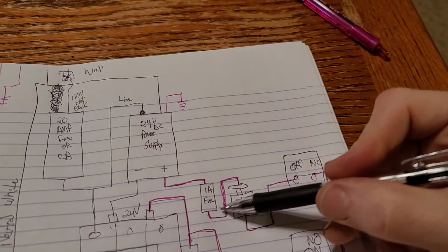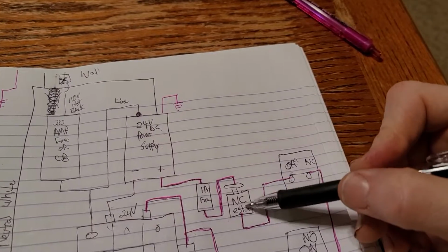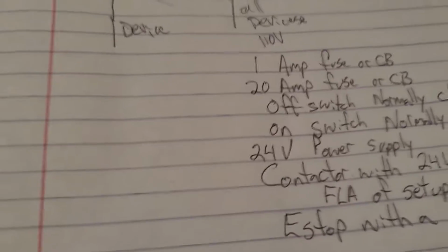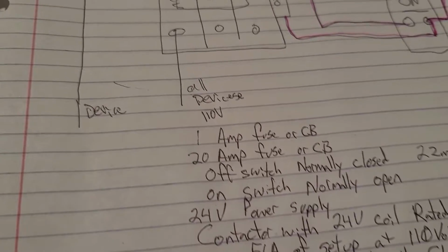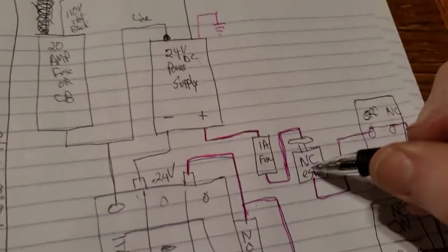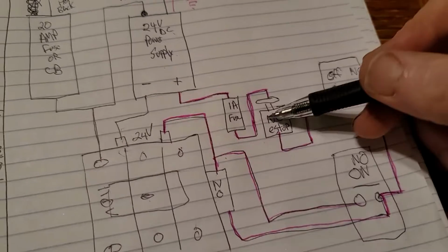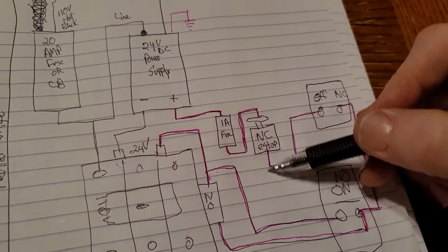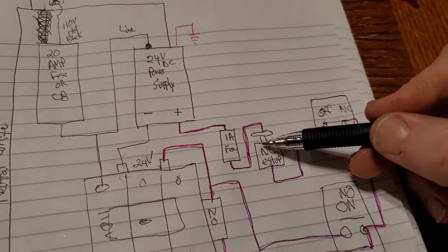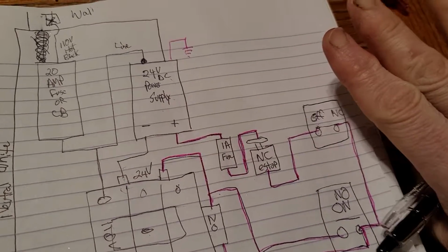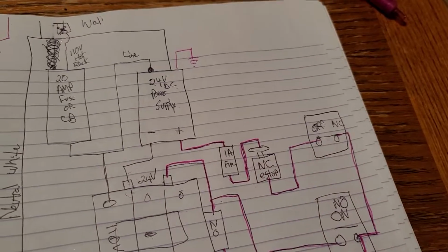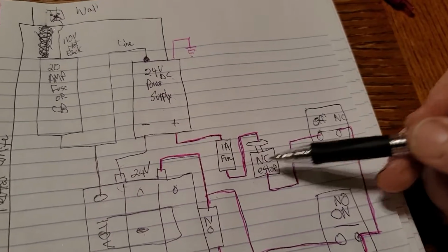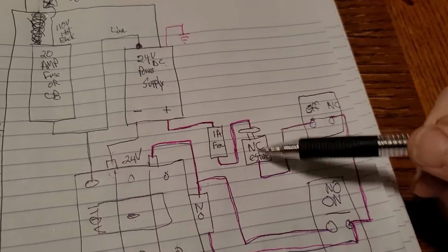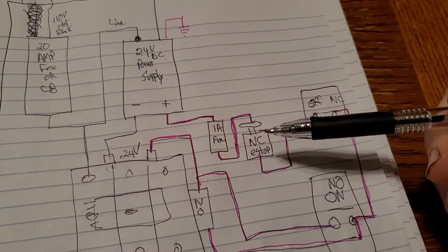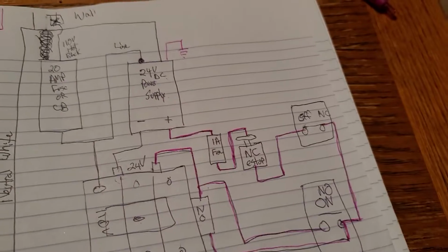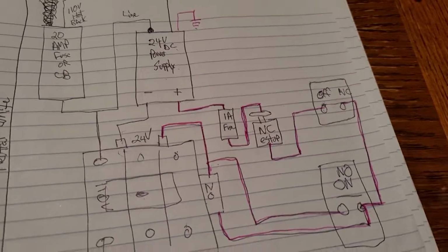Then you're going to run out of that 1 amp fuse and run it through your E-stop. And your E-stop, down here on the bottom, is a normally closed contact. That's why you'll see me say NC. Anytime you see NC, that means normally closed. So it's normally closed, so power is going to freely flow through it until you hit this button. And when you hit that button and plunge it, power's disconnected from there. But this is not the off button. This is a true E-stop. You can put this wherever you want. You put it on top of your box or over by your controls. But when you slam that, it's going to kill the power to everything that's powered by 110 volts.